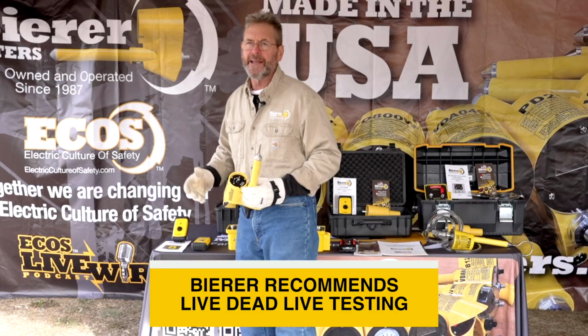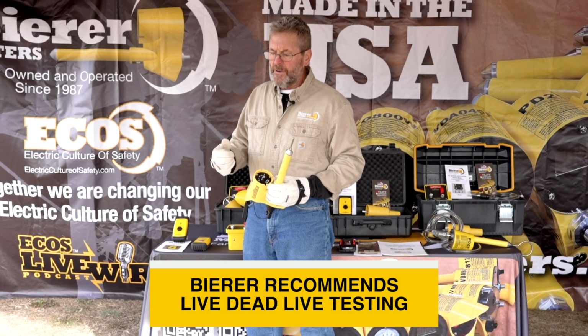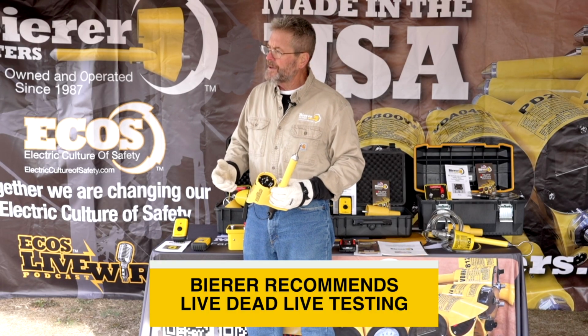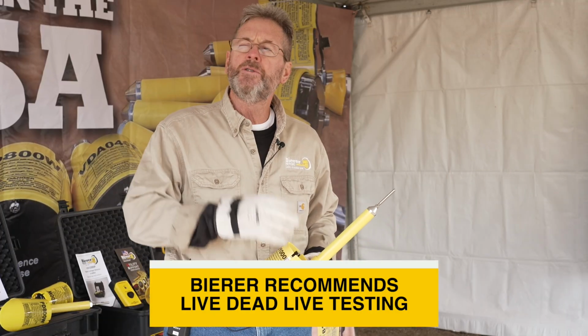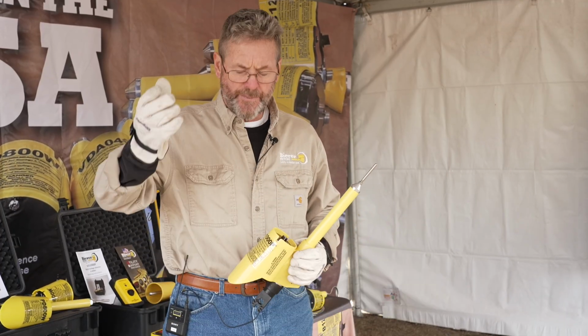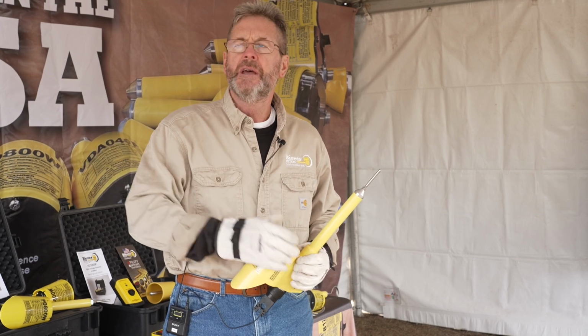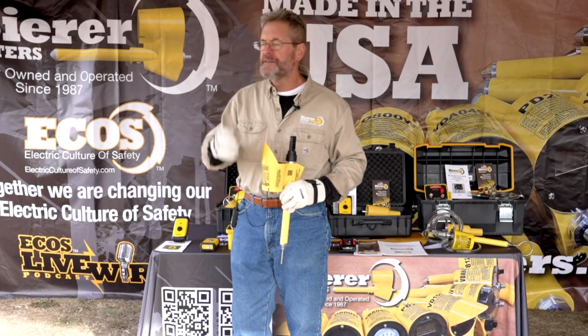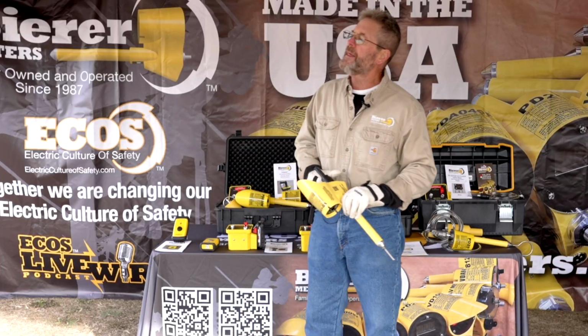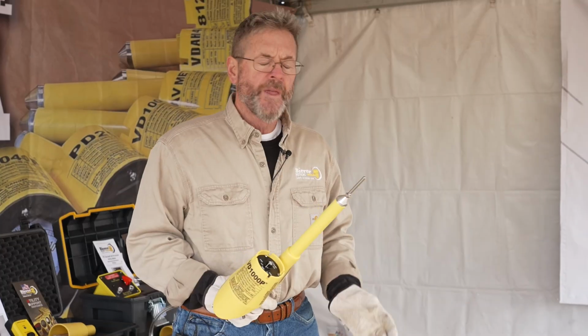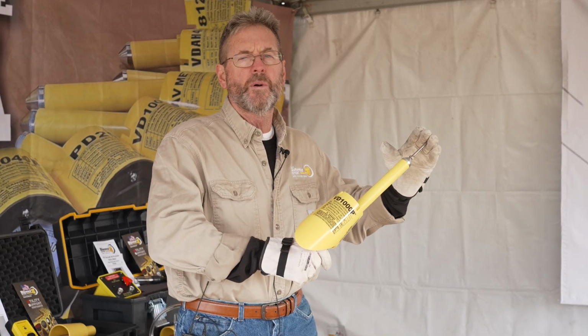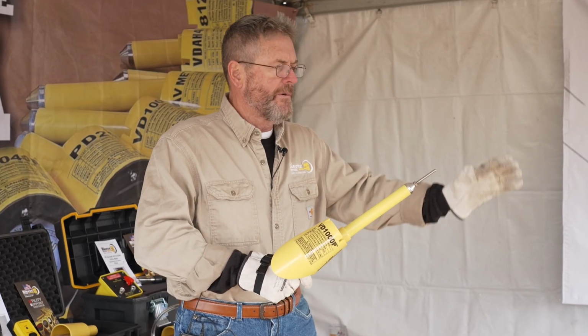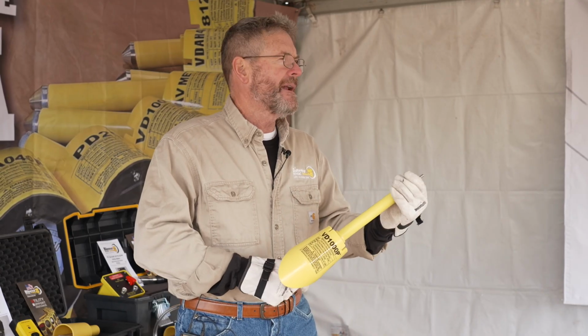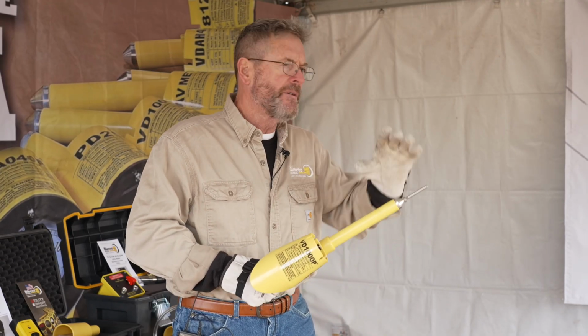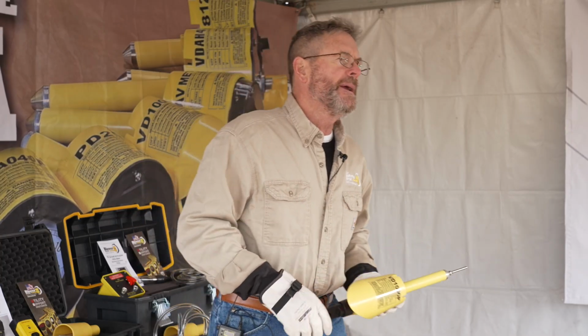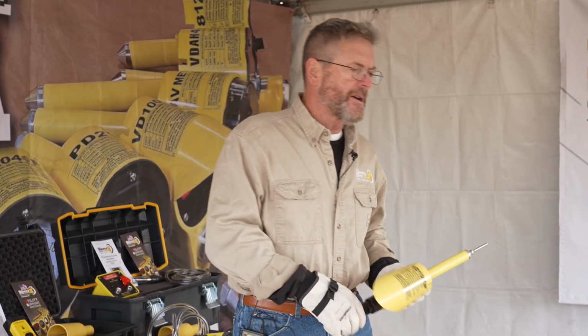We're going to perform our live test. If you're out in the field, say during storm restoration, and you're at an outage without a live known voltage source to perform a live test, we're going to de-energize that conductor, go to it, and make direct contact, which is super important. If you're working with a lot of capacitance, coupling capacitance, or induction flowing around you everywhere, Bierer Meters recommends that you always use direct contact tools.